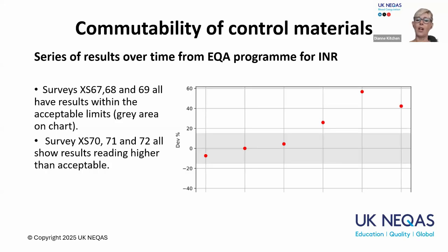So we've got about 3,500 devices that get checked en masse 4 times a year. This chart is showing you deviation from the median. The median is the optimum result, if you like, and that's the 0 line. The grey band of shading around that is what we have for our acceptable limits, which we deem to be 15% either side of the median.